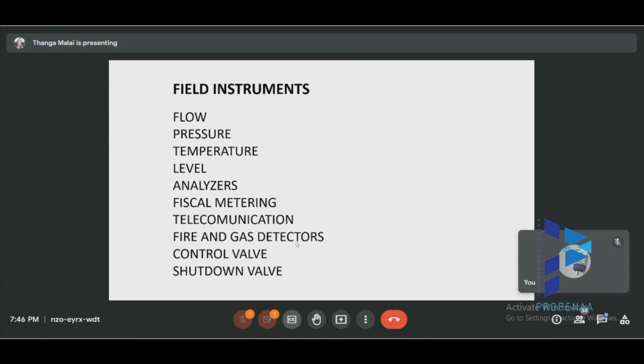If another gas detector activates, two detectors activate, then it is really a gas leak. Then the operator will have handheld detectors they can use with the hand, bringing the detector to the place to find out if there's a real gas leak. If there's a real leak, they will immediately shut down that particular area and fix it, because they know where the leak is, whether it's a flange leak or some other leak.